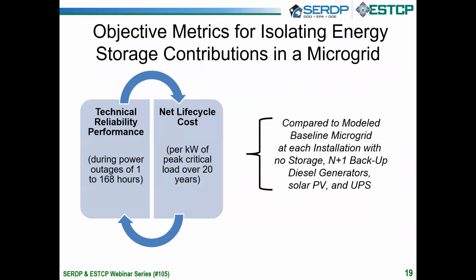So let's think about and examine this comparison. First of all, what are we talking about when we talk about reliability? We're specifically talking about the reliability during a grid outage when the microgrid is islanded from the commercial grid. And we want to understand the likelihood of being able to achieve the power to support critical loads from between 1 hour to a week-long outage. The results we'll show you will be for that duration of outage and shorter durations, but are applicable for longer outages as well. And we also want to understand the net life cycle costs.